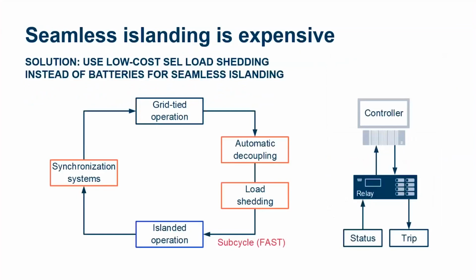With relays, the cost of seamless islanding has been reduced. Many of our customers perceive seamless islanding as expensive because they believe it requires battery. And that is not true. In the very first job we did in 2002, we didn't have batteries, yet we had seamless islanding. How do you do it? Well, you select loads that aren't critical, things like ventilating, heating, chillers, things that you can turn off. And you use SEL relays to turn them off in milliseconds so that when you island, when you separate from the grid, your limited DER capacity, the batteries, photovoltaics, the generators you have online, can carry your critical load.